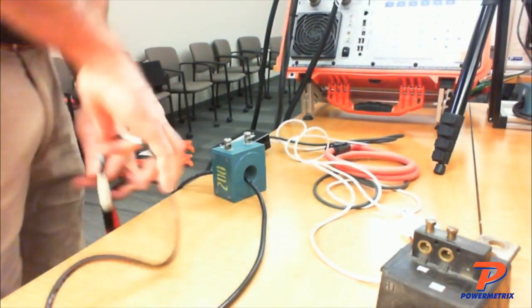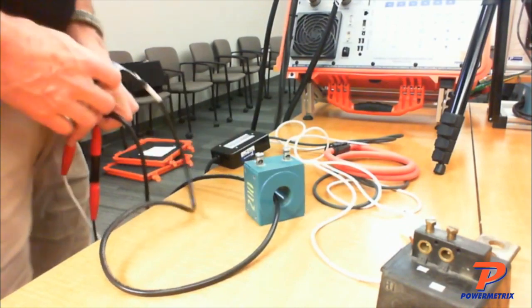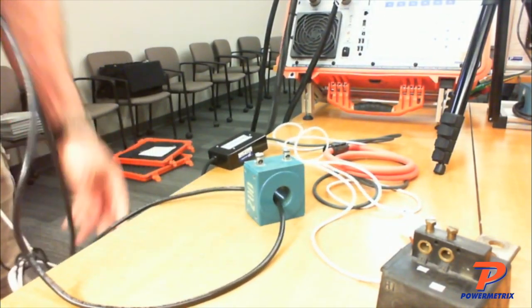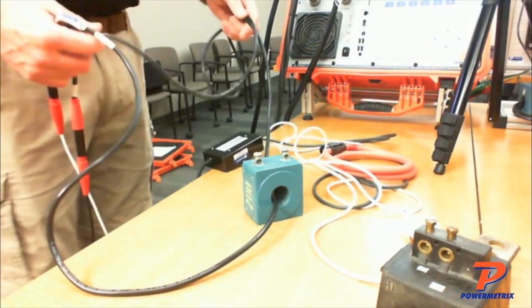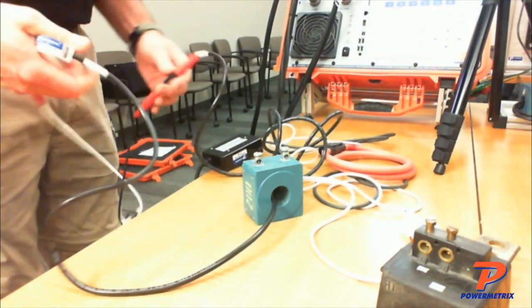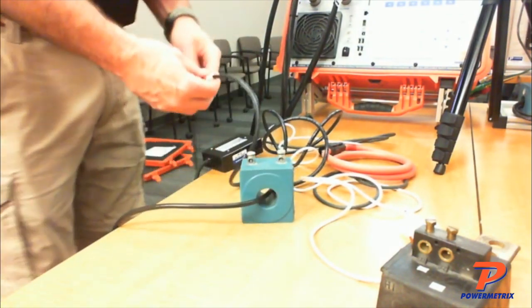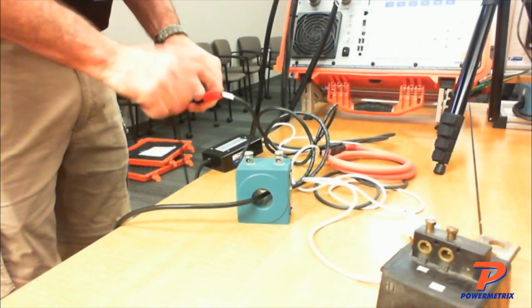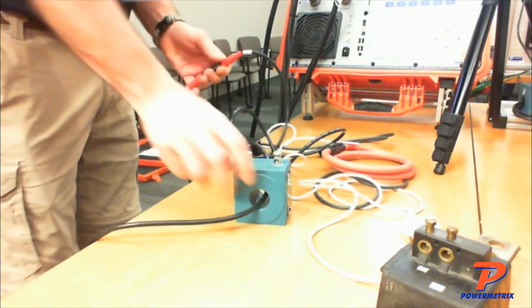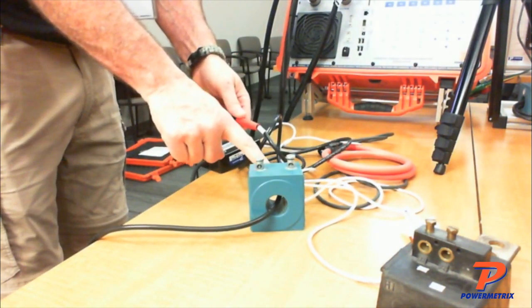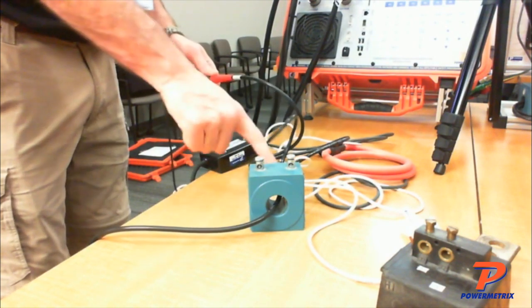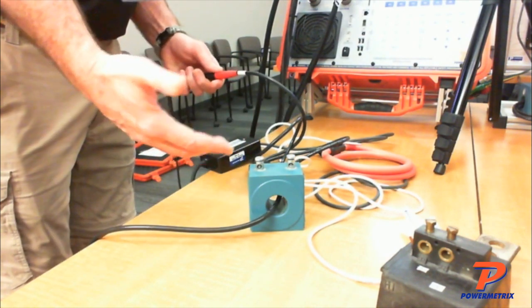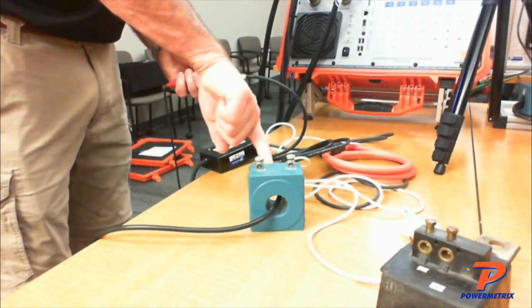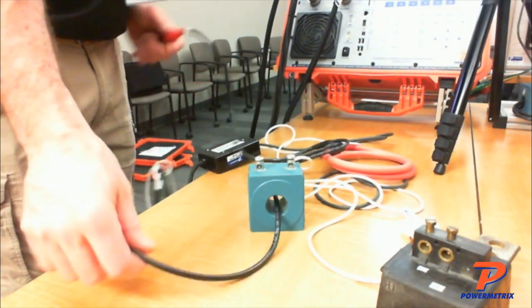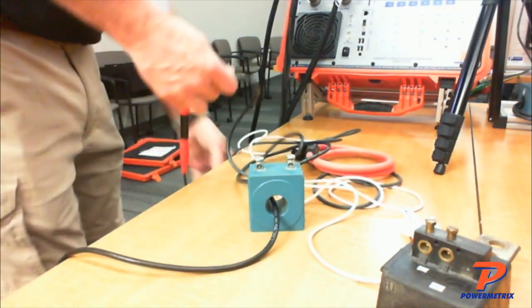Okay, so I've got my CT here. It's got a 200:5 CT. This time I'm using a drive cable because it's a donut CT. You just have to remember you want this drive end. See, this end is my drive end. I want to make sure my drive end is on the dot side of the CT, because I'm driving into the CT the same as you would in the field. The current would go this way, right? I'm coming into the dot side of the CT. Okay, so that's what I've done here.